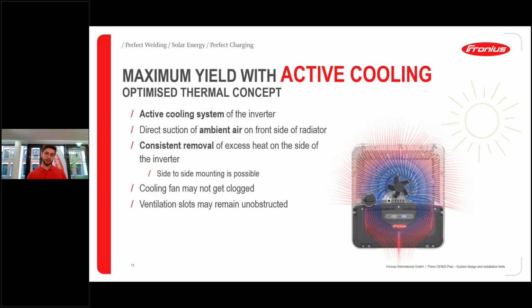I've already explained this. We have an actively cooled product with a centrally positioned fan, as we can see here, and we have really a heat distribution across the whole product. So on all sides, also at the bottom, we distribute the heat, and therefore we have a few advantages. We have a later derating behavior compared to a passively cooled system. We have a longer lifetime also of the electrical components, which is the biggest issue. And this is really the reason why we stick with the active cooling system. And here we can see how it works.